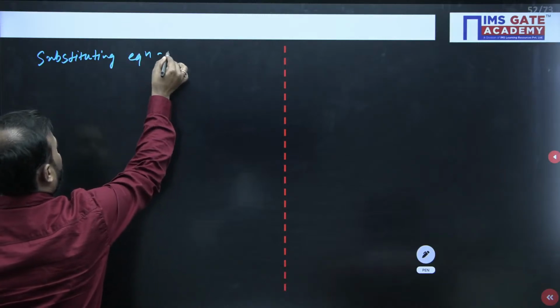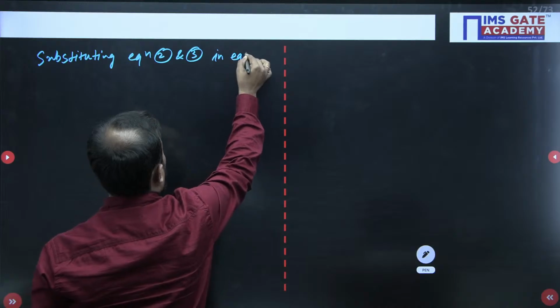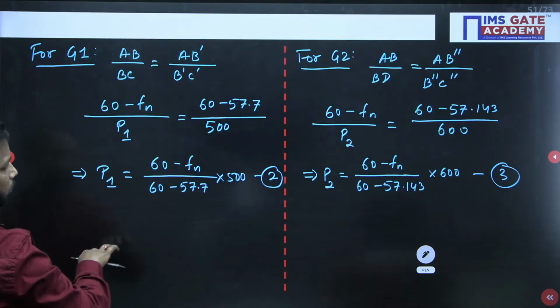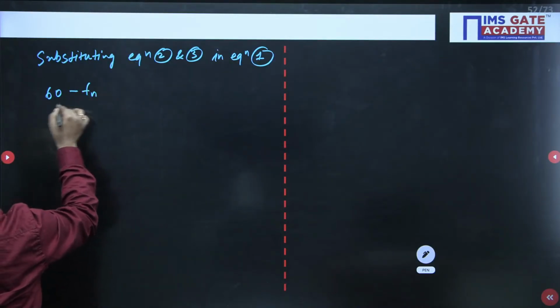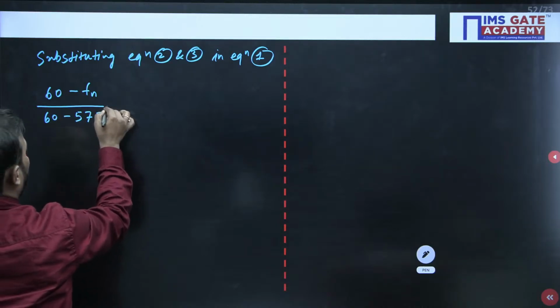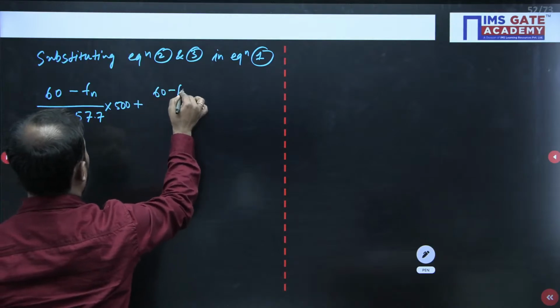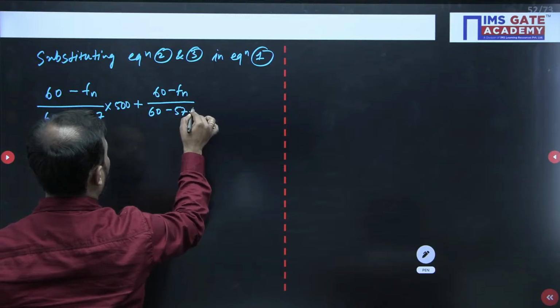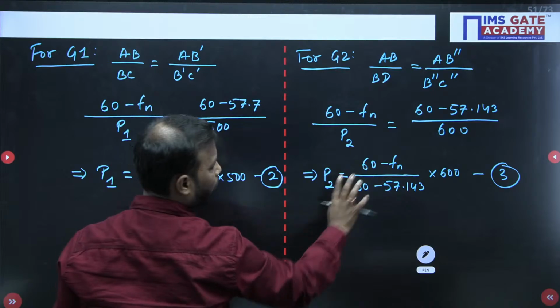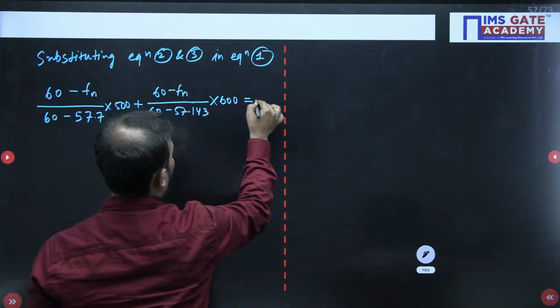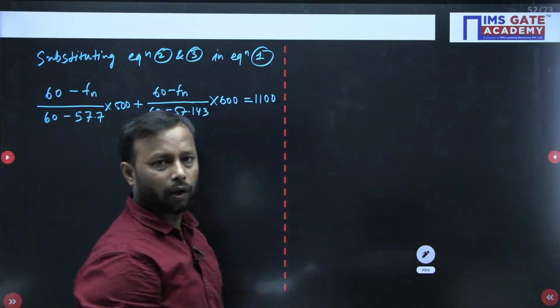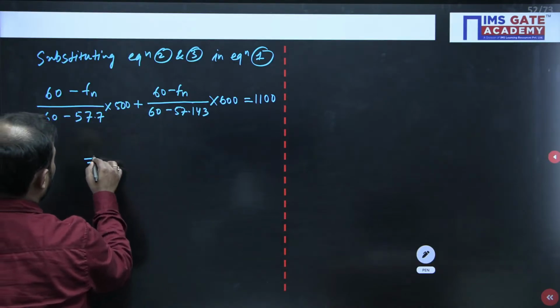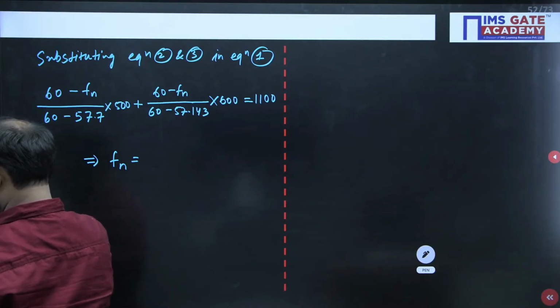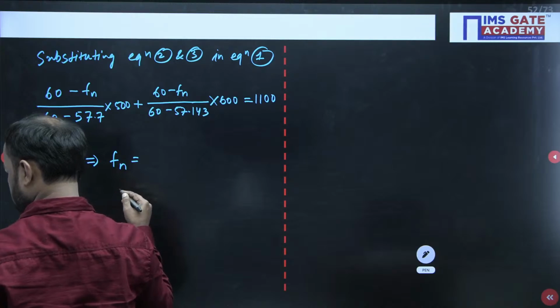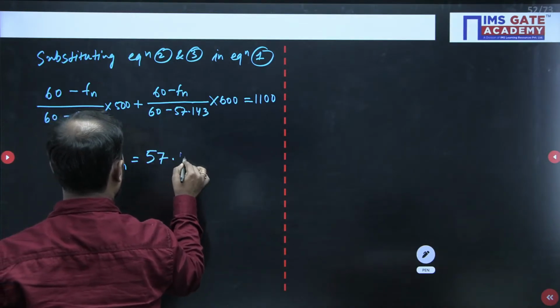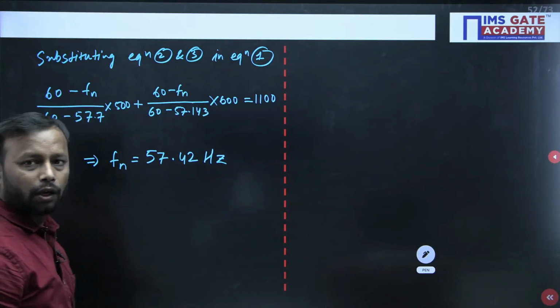Substituting equations 2 and 3 in equation 1: (60 minus Fn) divided by (60 minus 57.7) into 500, this is the P1 value, plus (60 minus Fn) divided by (60 minus 57.143) into 600, equal to 1100. So I have substituted in equation 1, and only one unknown is present, which is Fn. Solving this, we get Fn value as 57.42 hertz.